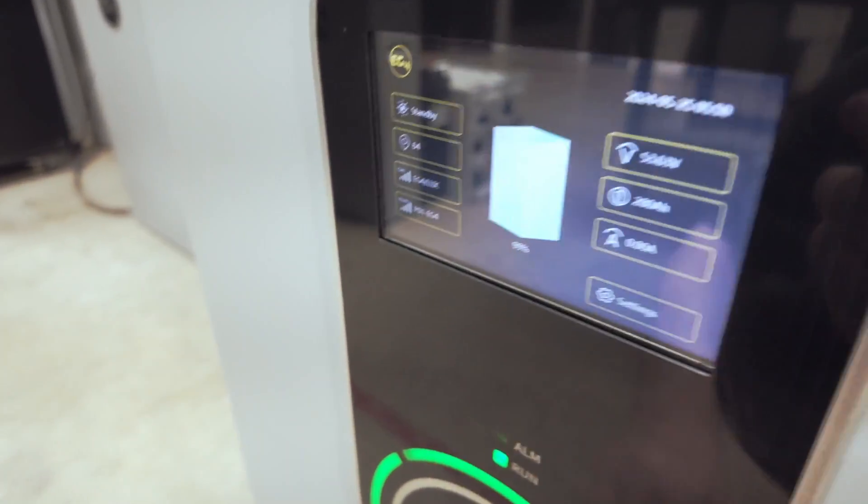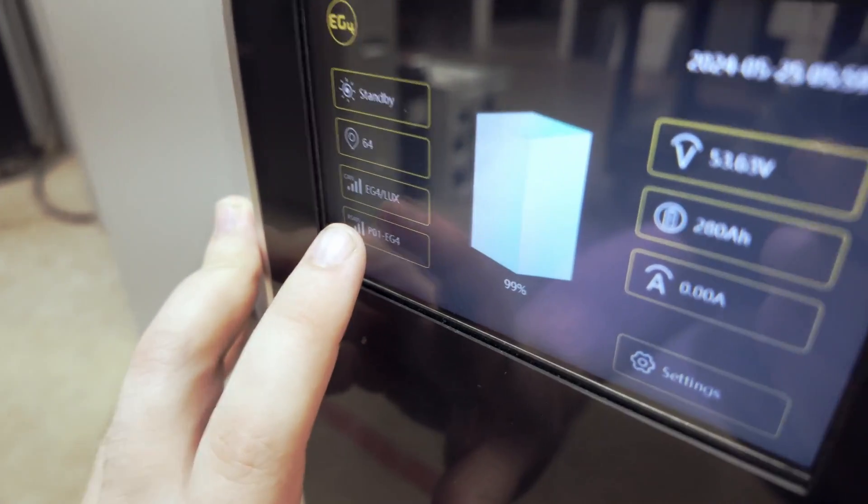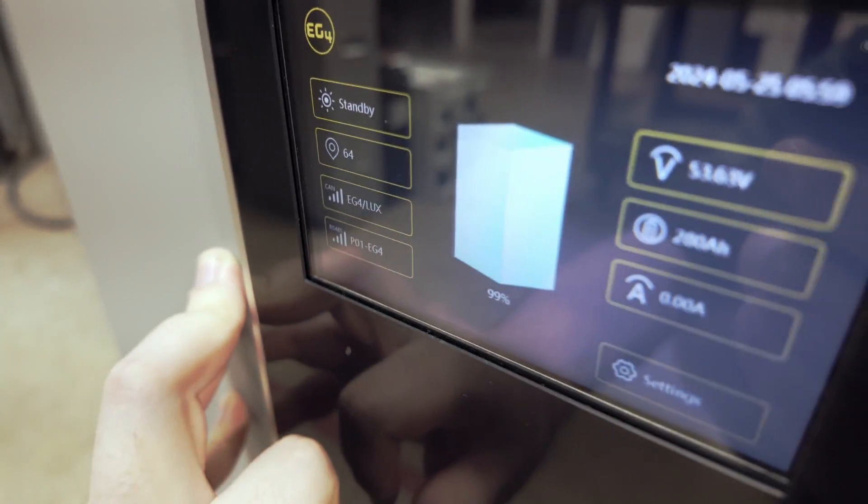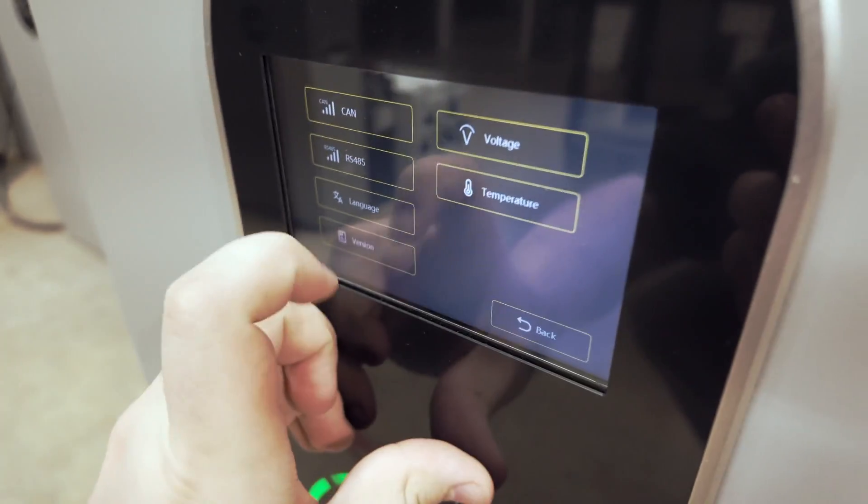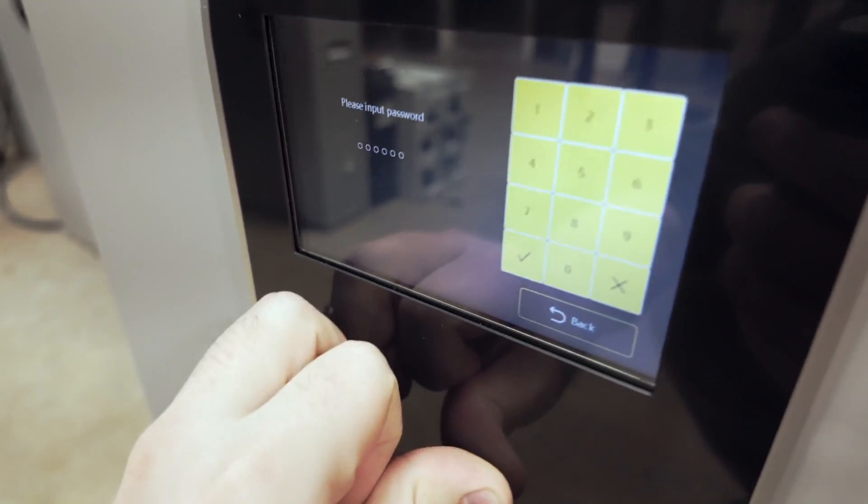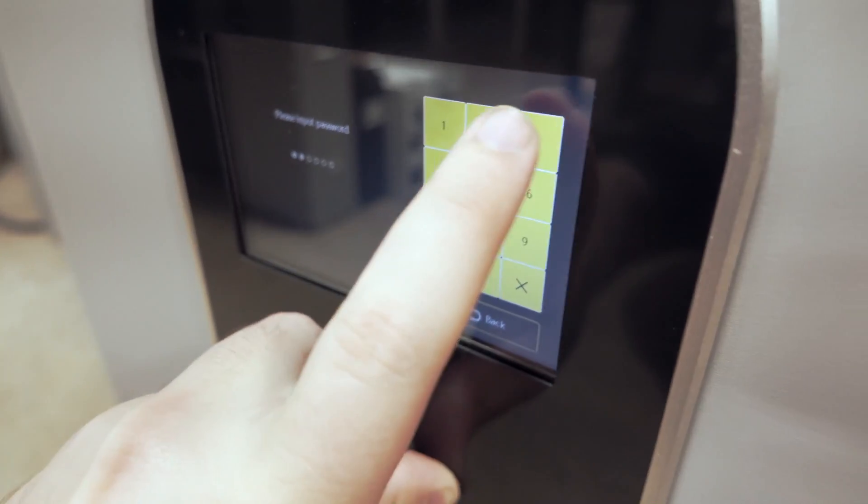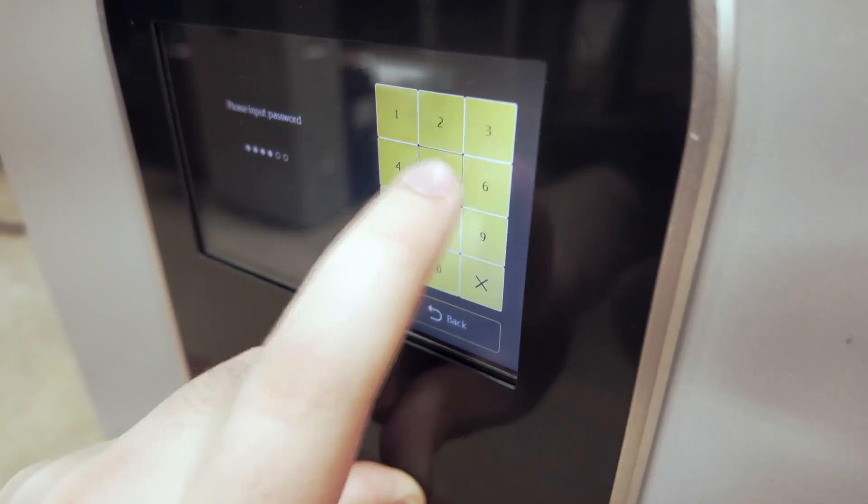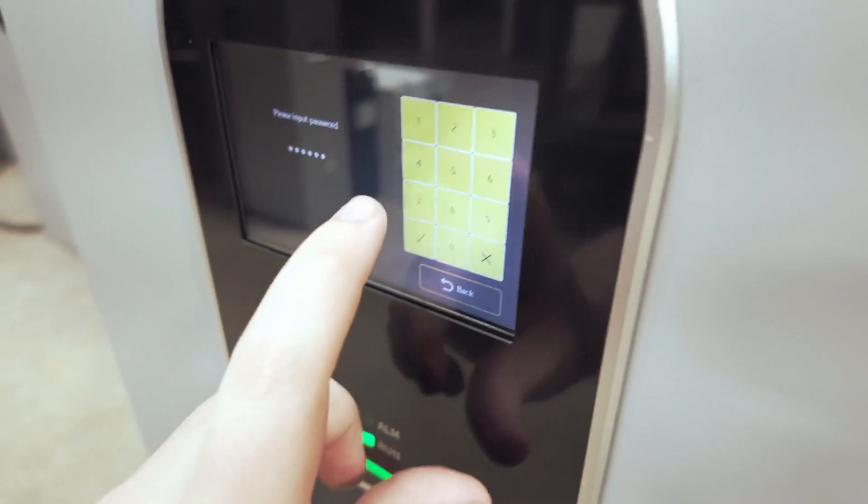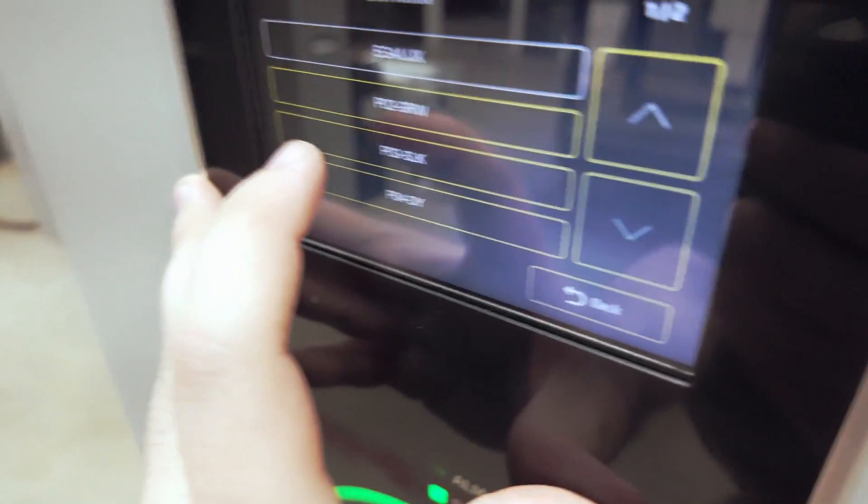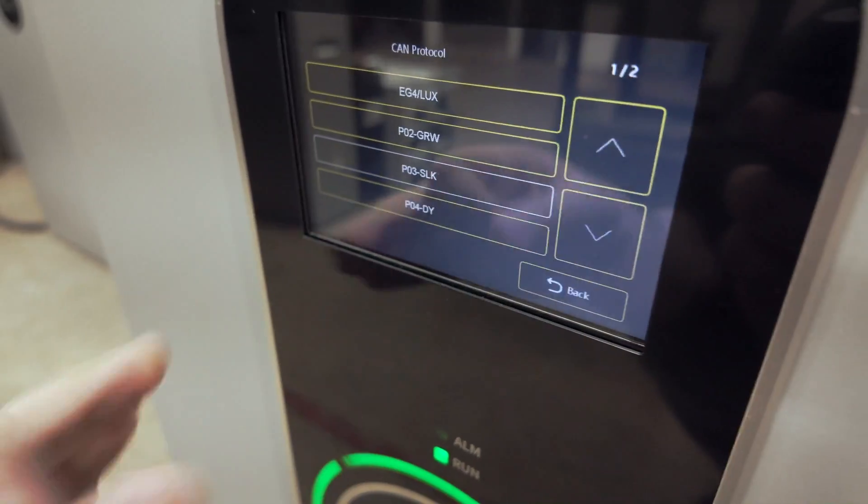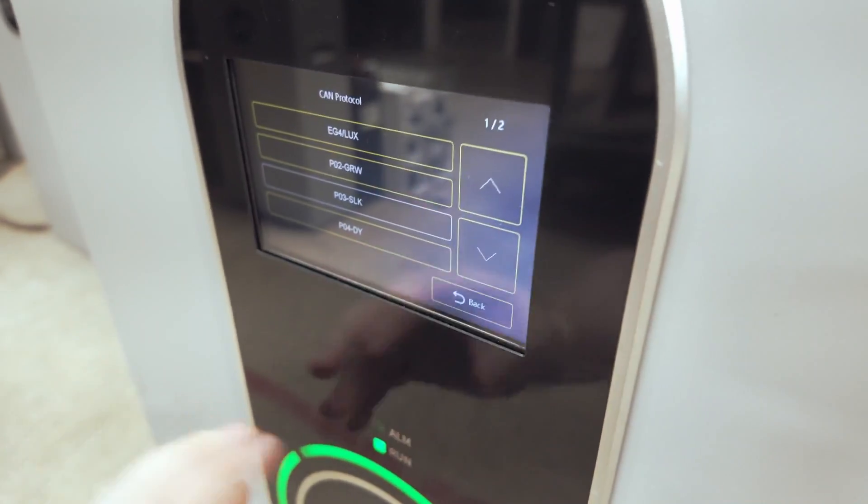Now on this screen, you will see that we default to the EG4 slash Lux protocol. Go to your settings, CAN communication. And then on here, you will want to select 123456 for the password, press the Enter button. And then you'll see SLK is the protocol we want to select SLK for Solark. That's setting three, press back.